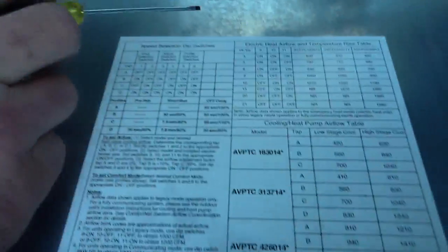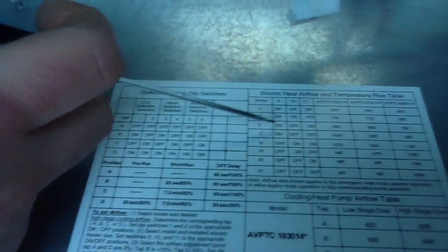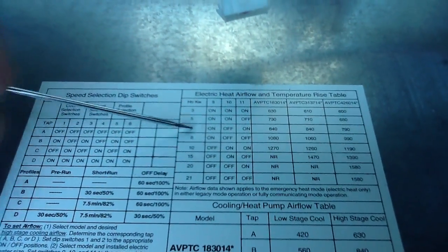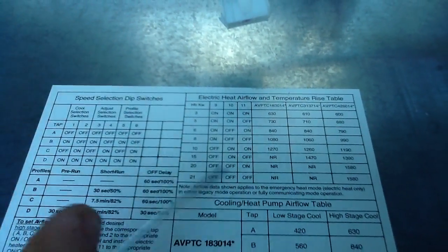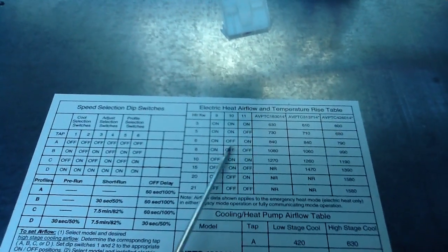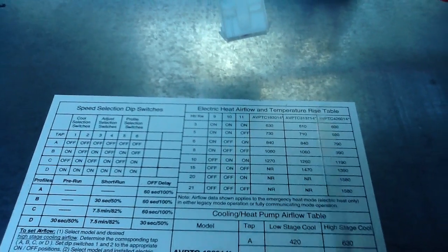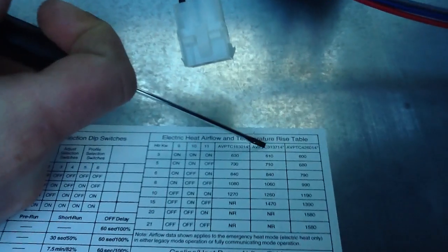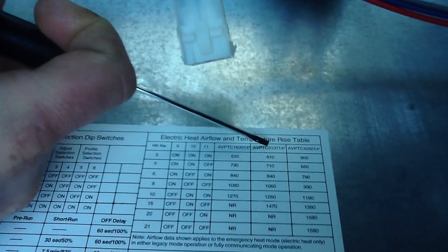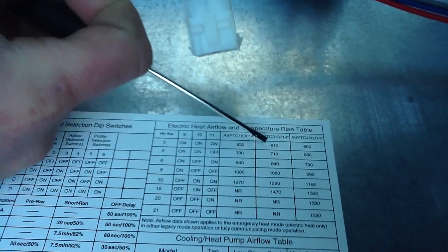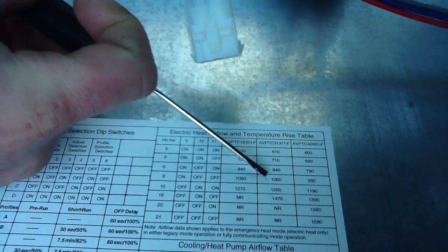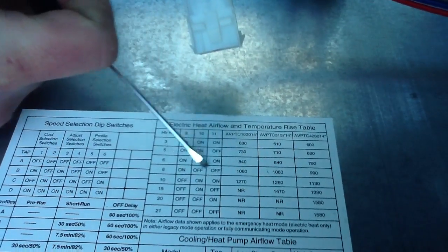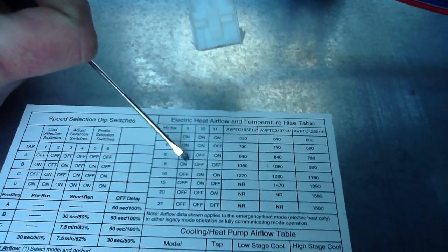Then you go down to your kilowatts. We're going to be using 8KW heat - it's on, off, off. AVPTC313714 is the one we're using. You match it down here at 1060, so it matches up - on, off, off.